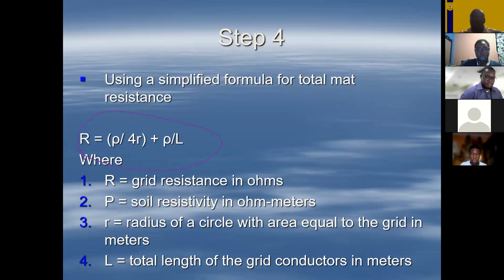So you have a circle which is the same area as the square grid. The square grid is 100 by 100, 10,000 square meters. We're going to find the radius of a circle which has an equivalent area - that's for that R. And L is the total length of the grid conductors in meters, which we had already calculated.